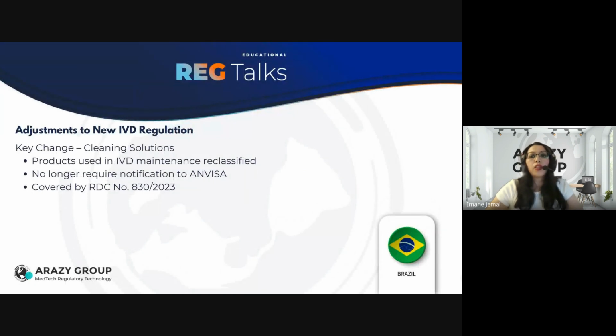So under the new regulation, which has been in effect since June of last year, Anvisa has clarified that cleaning solutions used exclusively for IVD equipment maintenance are no longer notifiable products. These items may now be freely marketed without prior authorization, as they are considered low health risk.